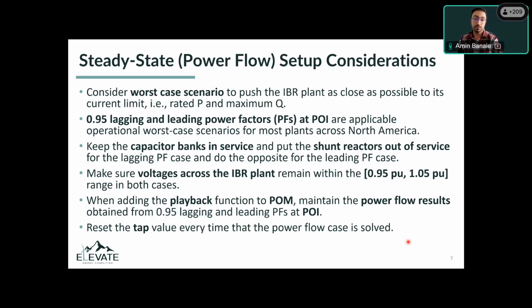And for almost 90% of the plants across North America, ISOs and utilities, maximum Q is at 0.95 lagging and leading power factor at POI. That's what we consider for our studies to make sure that we are not going beyond what's required for the IBR plant at POI. If the plant is connected to an area that has a different power factor requirement, you can consider that as the worst case. But as I said, in 90% of the cases, it's 0.95 lagging and leading.